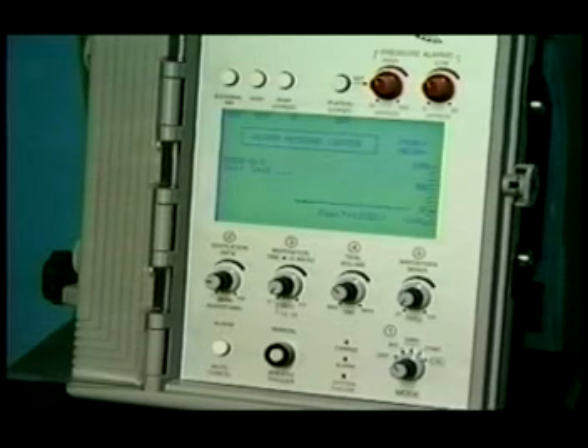Turning power on causes the unit to perform a self-check. This process checks power, battery, memory, control panel settings, and transducer calibration. It normally takes about 2 or 3 seconds to perform, and then operation is allowed to begin. Do not connect the ventilator circuit to the patient until self-check completes. This prevents any pressure from entering the ventilator circuit and causing a false transducer calibration alarm.